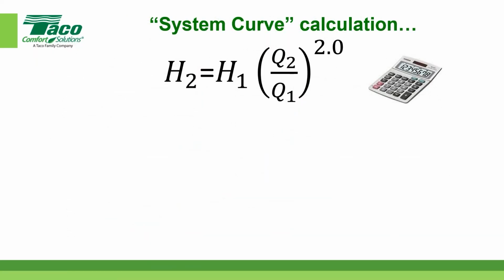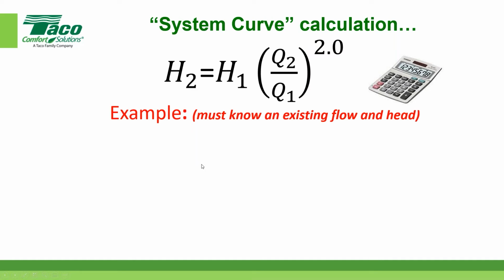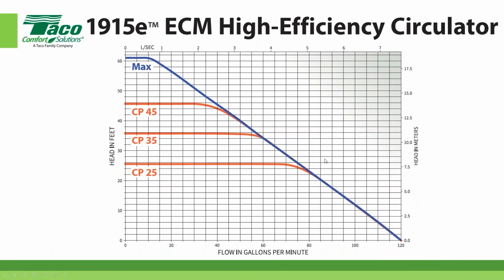Now, how can we predict where that's going to be? Yes, there's a calculation for that. Just like there's an app for everything, there's usually some kind of calculation to show you how to figure out what the system curve is. In order to know, you must know one thing, or do a pretty good estimate at one point, and then you'll get a fairly good result, depending on how good that information was. You would be able to calculate what the estimated pressure drop would be if you shoved more water through the system at a given point, or less. And that's what this next slide gives you an idea of.